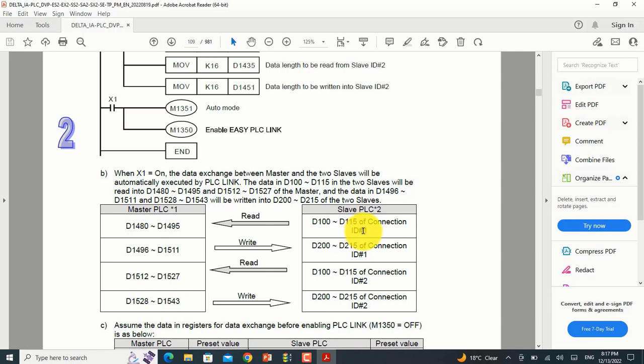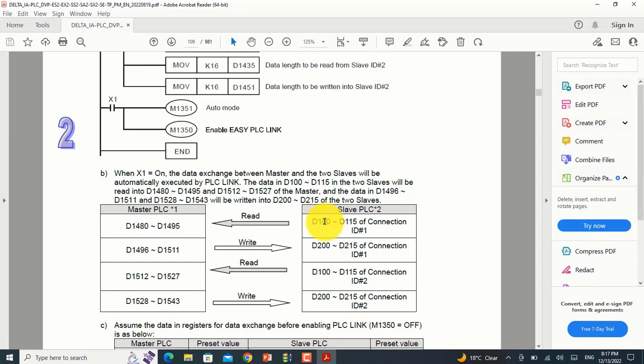For slave ID1, for writing: if you write a value into D1496 on the master, it will automatically move into D200 on the slave. By PLC Link this is very easy to use for communication between PLCs over distances like one kilometer or 500 meters. If you have any questions please raise them in the comment box and our team will answer as soon as possible. Bye!